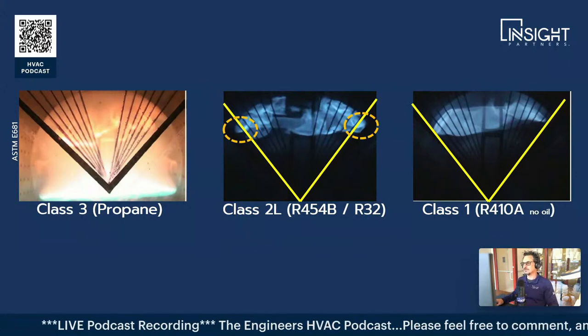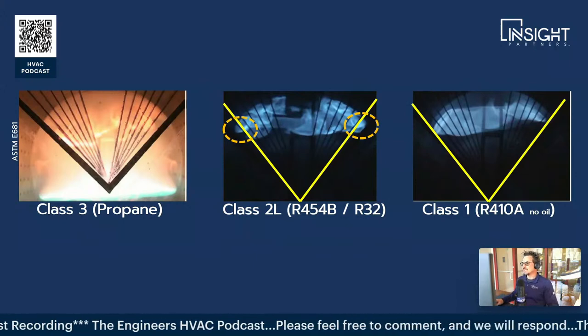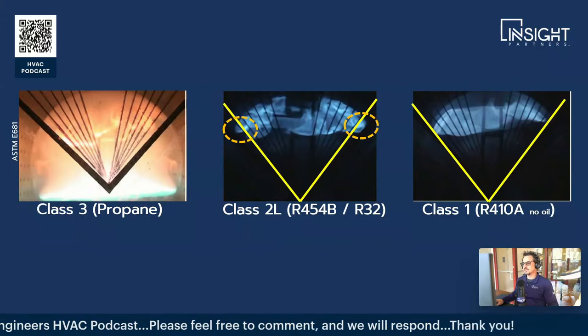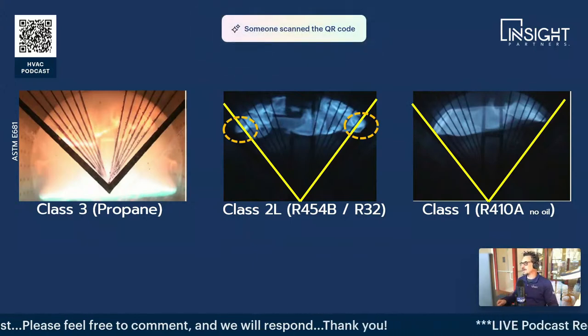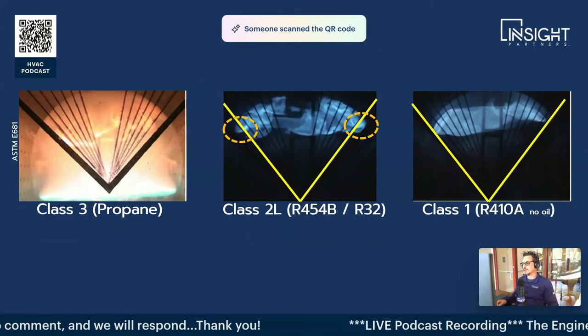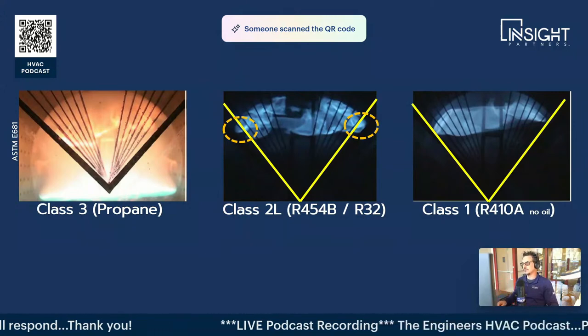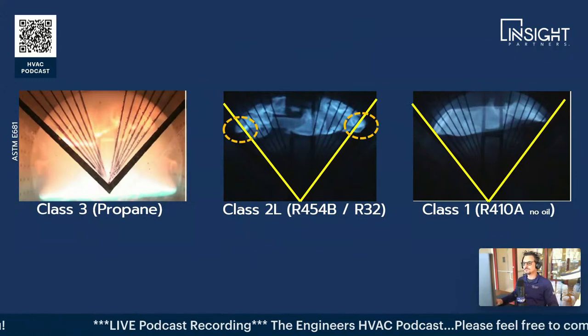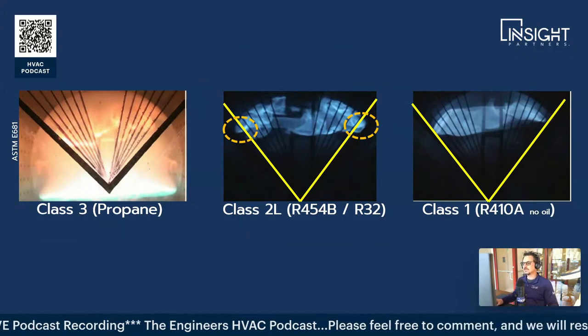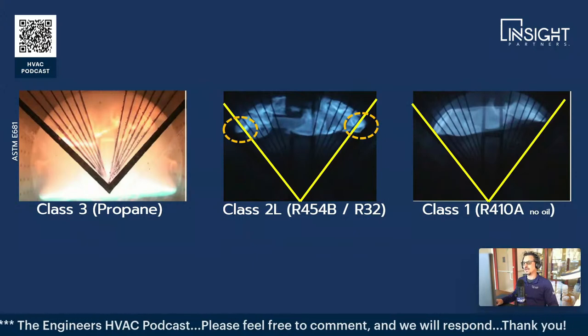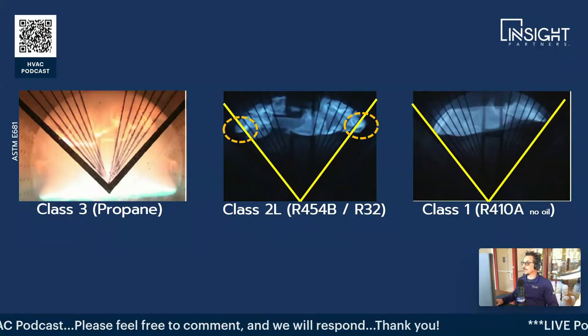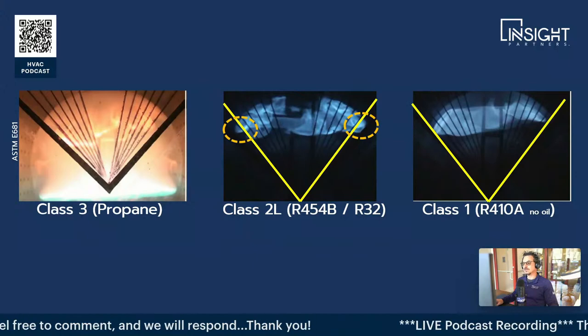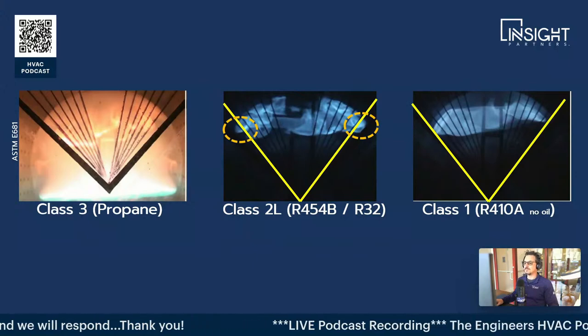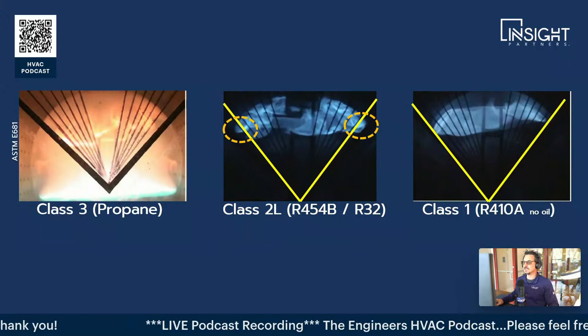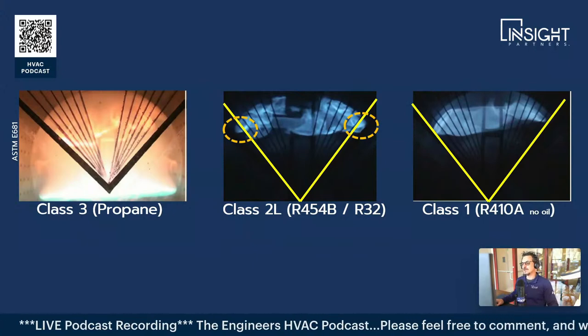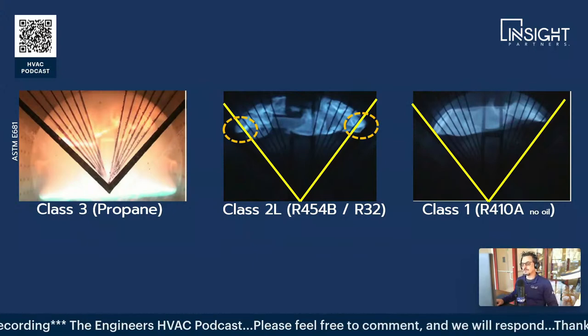And you could actually go on YouTube - I was going to show one of these videos, but since it's not scientific, I didn't want to show it. But you can see people trying to ignite the A2L refrigerants, and it's just really, you may get a little puff if it's at extremely high velocity. So anyway, that set my mind at ease regarding that. Even the 410A will create a flame under the right conditions, as you can see here, which is extremely hard to create. So safe handling and maintenance practices should be essentially the same between A1 and A2Ls.